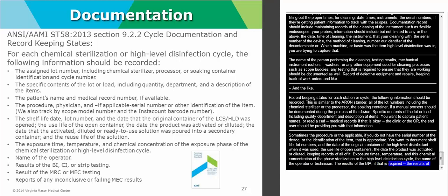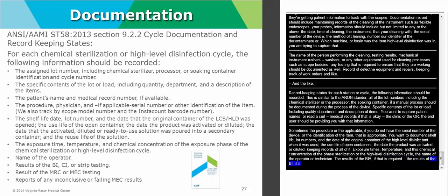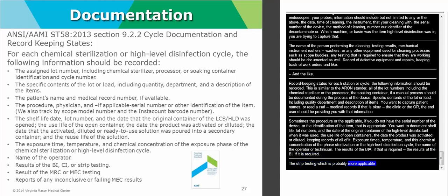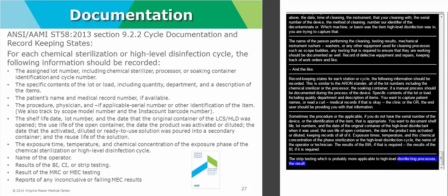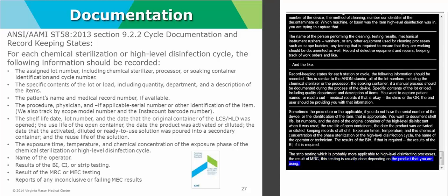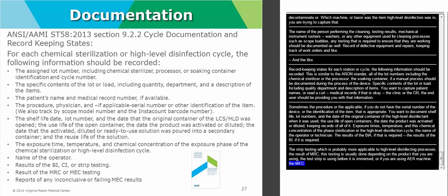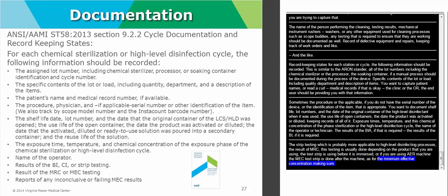Your chemical indicator, again, that's for sterilization, or your strip testing, which would probably be more applicable to high-level disinfecting processes. The result of your MRC or your MEC testing is usually done depending on the product that you're using. The test strip is done either before the device is immersed into a chemical disinfectant, or if you're using an AER machine, the MEC test strip is done at the end of the cycle, just depending on what product you're using. And that's for the minimum effective concentration, making sure that the active ingredients in that high-level disinfectant are at their best to ensure that the product is coming out high-level disinfected.